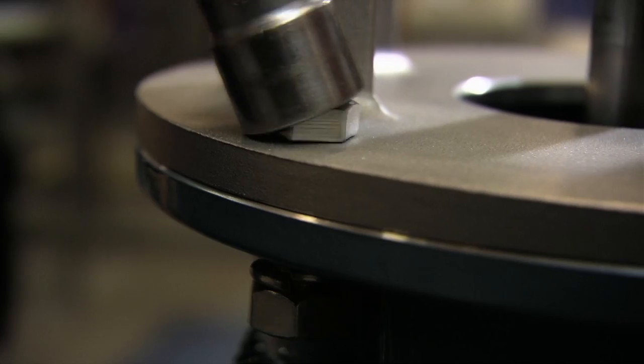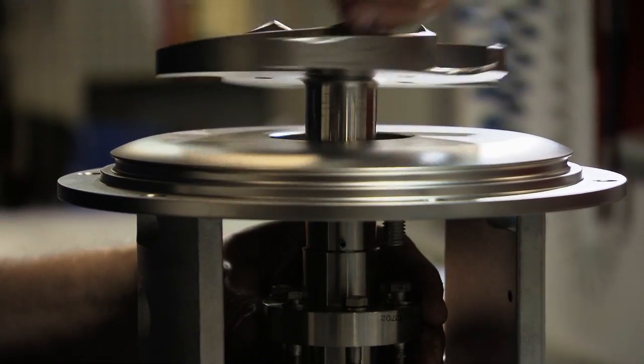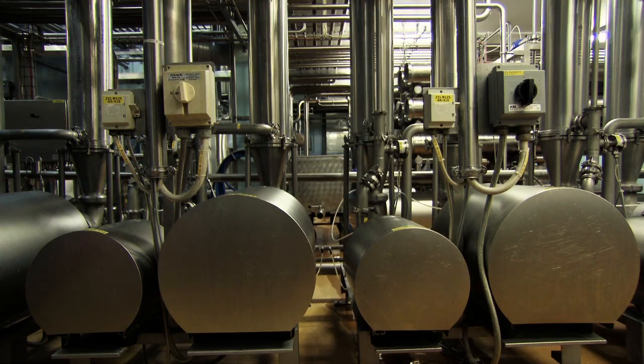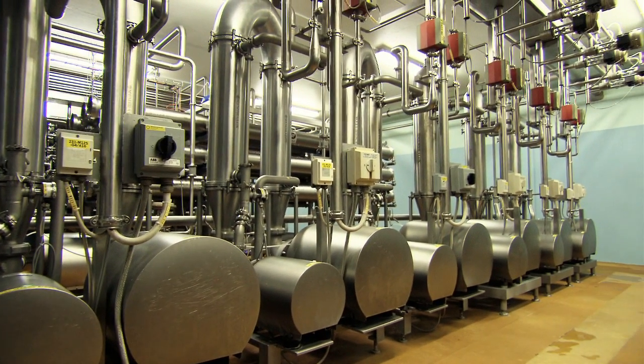Matching the configuration of each pump to its application helps processors save money while reducing greenhouse emissions. It is important to choose a well-designed pump. Close tolerances and optimised internal design are the keys to performance and require a robust construction. Closer tolerances also provide less internal fluid recirculation, and this protects product integrity as well as saving costs and energy during processing.